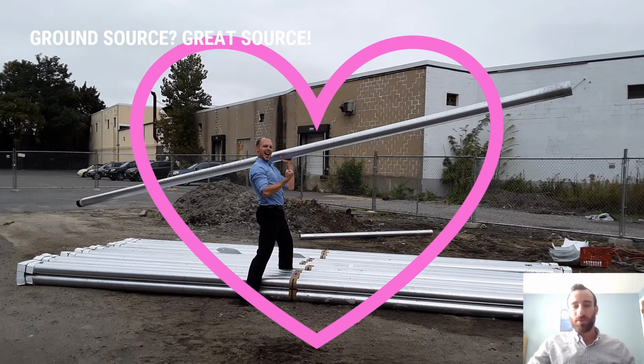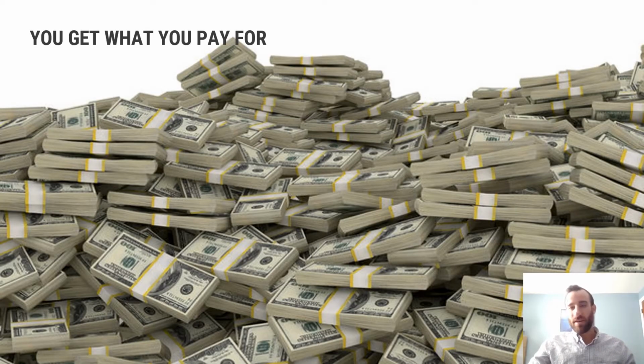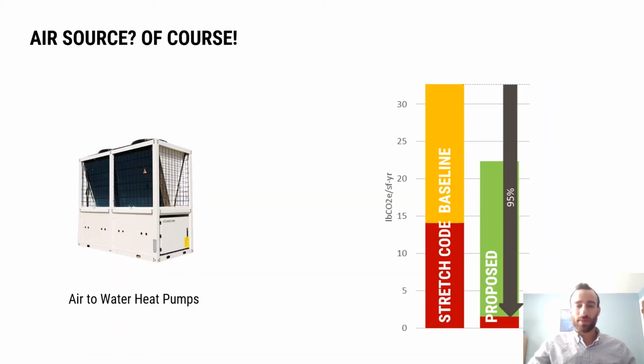So ground source heat pumps or geothermal are really great. They're extremely efficient sources of heating, but they're also really expensive. And that's partially because it's really expensive to drill wells and also because it takes up a lot of space to drill all those wells for geothermal. So it's becoming more and more common in our work instead to use air to water heat pumps. And that's because we can typically fit a lot more air to water heat pumps on a project and get much higher levels of electrification, much more fossil fuel reductions, even though there's a slight penalty in terms of efficiency compared to ground source heat pumps.